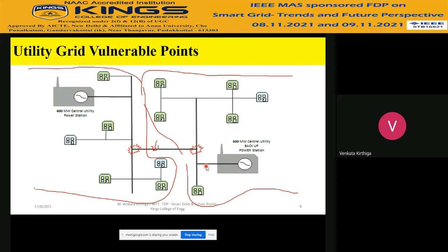Now, when this tie line gets removed, what is the consequence? This is the only line which connects these two systems. So there can be a huge load shedding required in order to balance. Suppose if I have a 600 megawatt system here, and all of a sudden there is a sinking point, or some heavy load has come into the picture unexpectedly, or unexpectedly all the loads have come into picture at the same time, which was not expected.